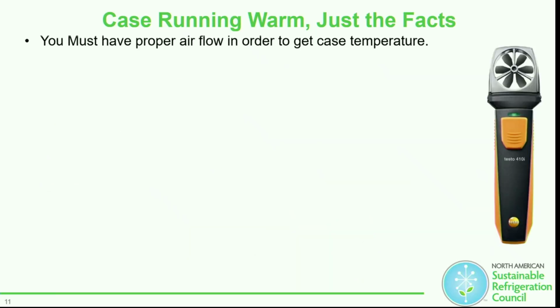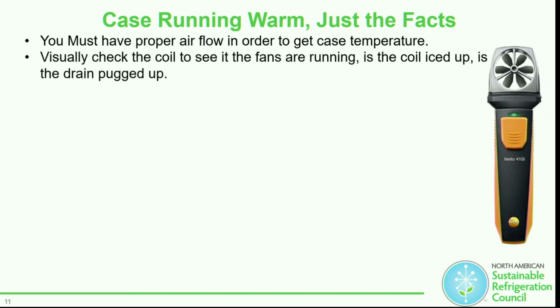Case running warm, it's just the facts. You must have proper airflow in order to get the case down to temperature, like we just discussed. Visually check the coil and see if the fans are running. Is the coil iced up or is the drain plugged?